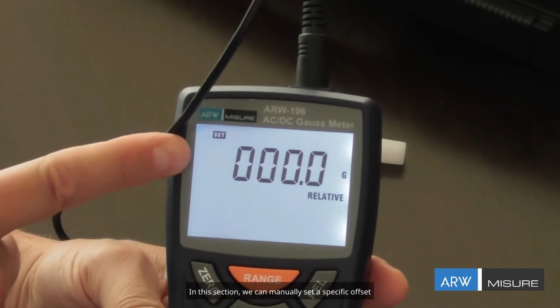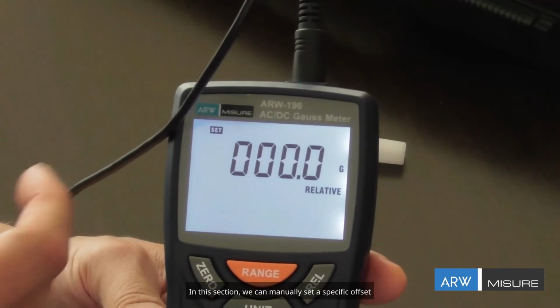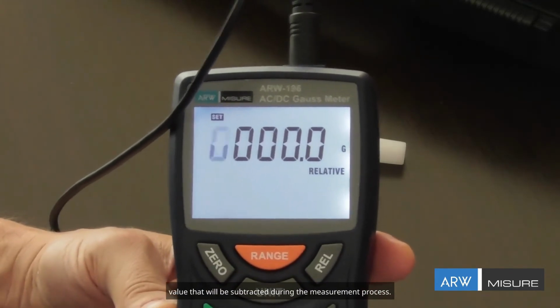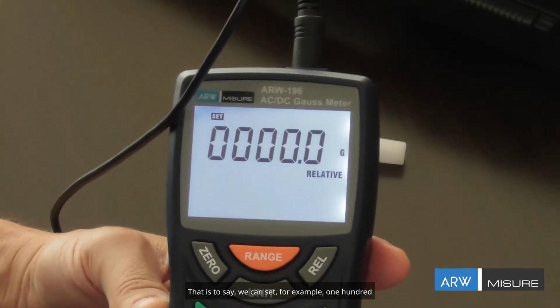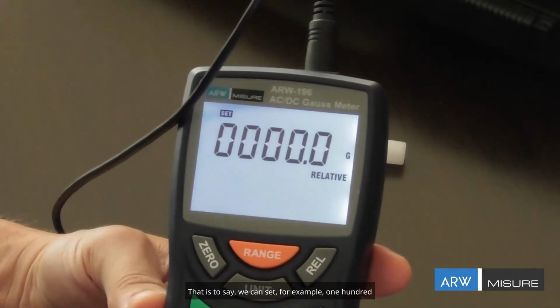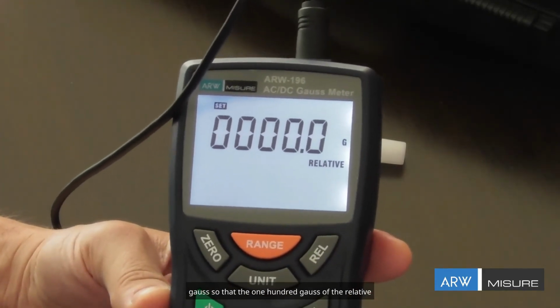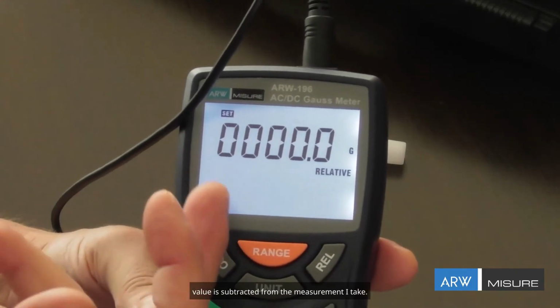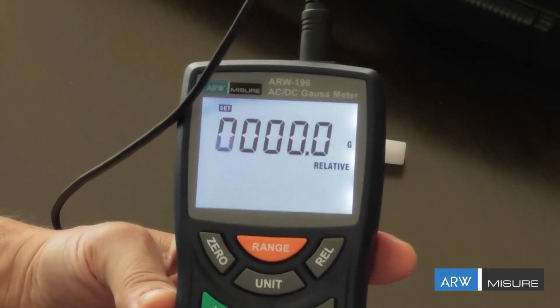In this section, we can manually set a specific offset value that will be subtracted during the measurement process. That is to say, we can set, for example, 100 Gauss, so that the 100 Gauss of the relative value is subtracted from the measurement I take.